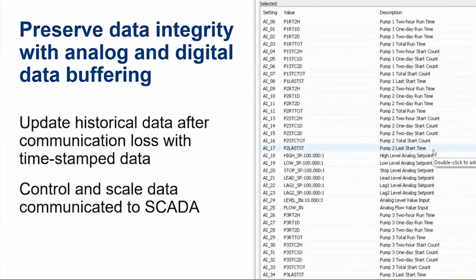Another thing that we're doing is we have an analog. We really like to use DNP3. It's an event-driven protocol, and what that does is it allows us to log historical data during communication failures or communication lapses. So you don't have to poll the device constantly. It's automatically buffering this analog and digital data. So what does that look like?